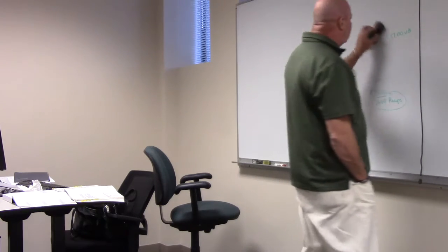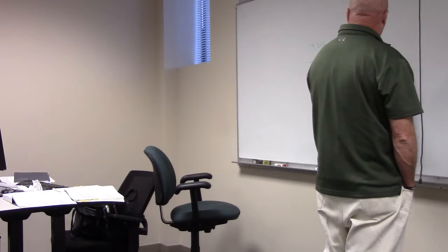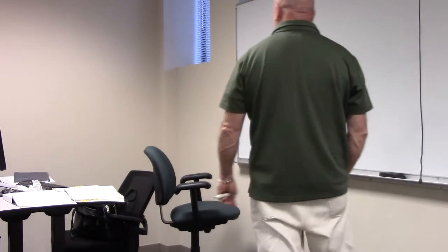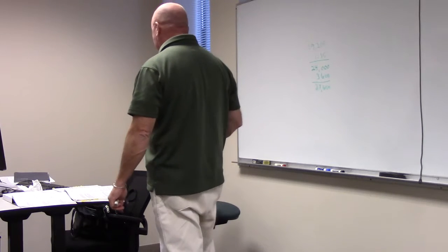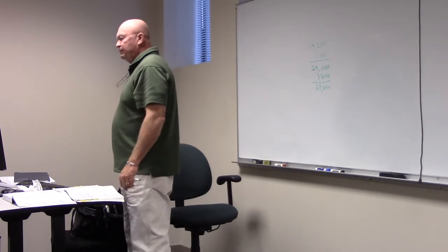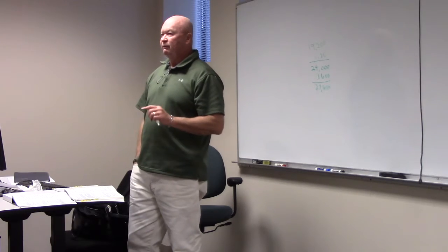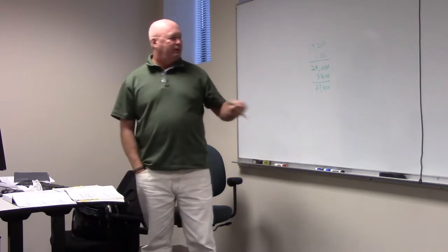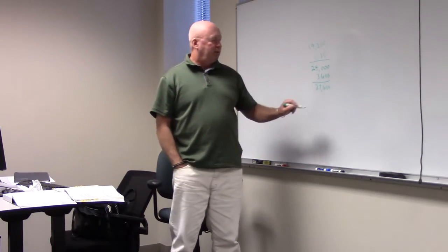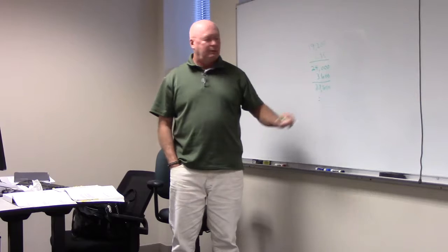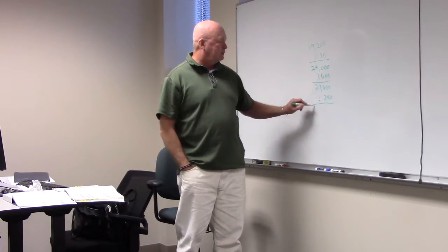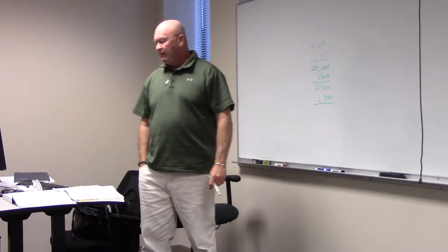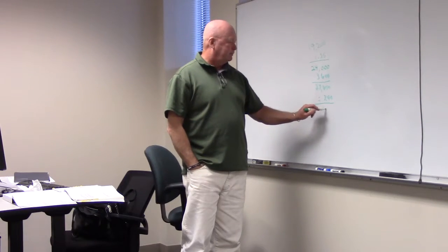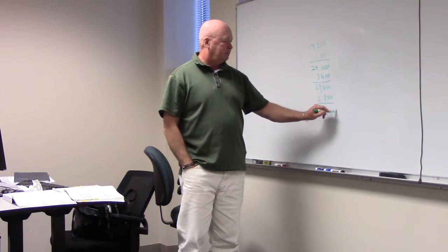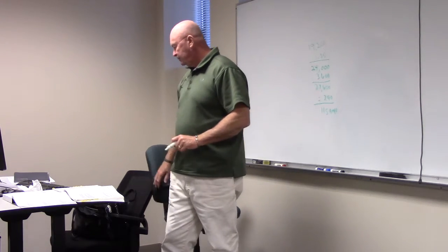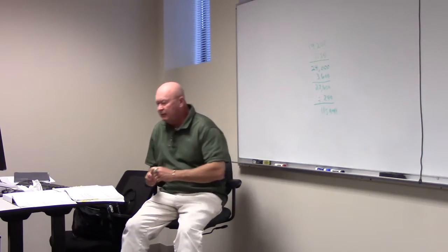Yes, sir. It told me my service was what? Single phase or three phase? In the description, what did it say? Single phase. What's the voltage? 120/240. So to get to amps, we're going to divide these volt-amps by how much? 240. Let's see what that gets us. Hopefully about 115. 115. Yeah, very good. There you go.